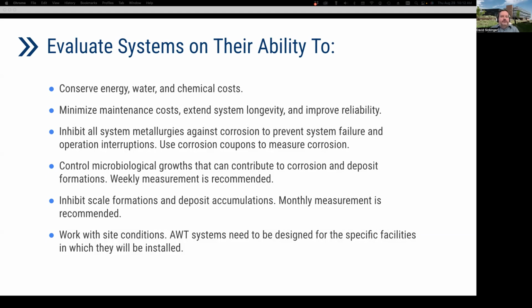Next three bullets are all linked to guidance found in the GSA P100, the facility standards for the Public Building Service. And in that document, it requires that a licensed water treatment specialist design the water treatment for cooling tower systems with consideration of the operational and maintenance need of all associated system equipment. So an AWT system must address these aspects, providing corrosion protection, controlling biological growth, inhibiting scaling, and meet environmental discharge regulations. And then the last bullet on this slide is, AWT systems that are designed and sized to work for specific facilities in which they will be installed and be compatible with the rest of the system equipment. So then next slide.